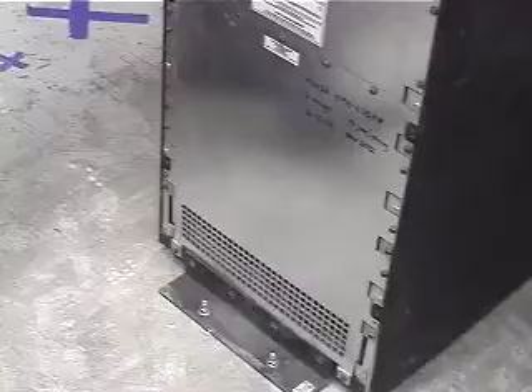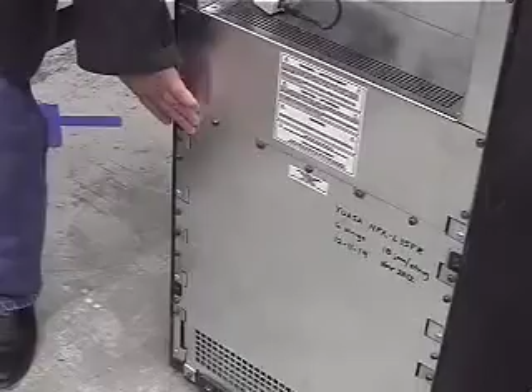In the book, you see on the front cover, we have this unit as a 20 kVA unit. One of the things you guys need to know is that in the future it is capable of being upgraded to 30 kVA if you ever found you needed to do that. Inside the unit down here is where your batteries are at. You've got, at full load 18 kW, an 18-minute runtime on it. So the lower your load, the longer your runtime is going to be.